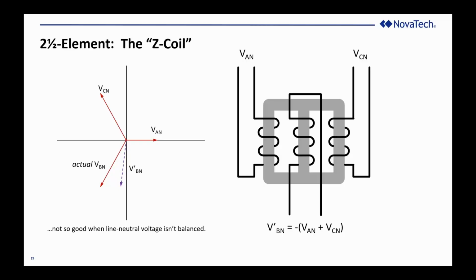Well, it works perfectly when the voltage is balanced. But if the voltage isn't balanced, then it produces a vector that is not equal to the B to neutral voltage, and the meter falls apart. It doesn't work. So this is what we refer to as the presumption of balance. How good is the presumption that three-phase to neutral voltages will be in balance? Well, the closer you are to the source, the closer you are to the generator. If you're up in the transmission system, the source impedance is very low. The balance of the A to neutral, B to neutral, and C to neutral voltages is probably going to be very good.